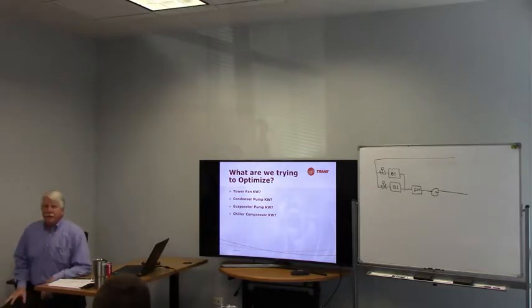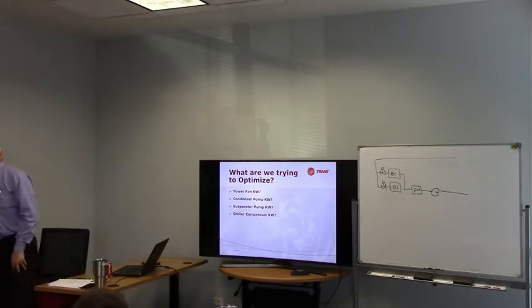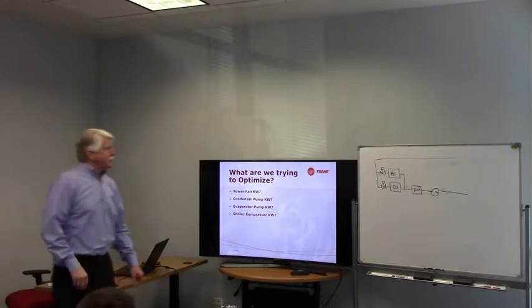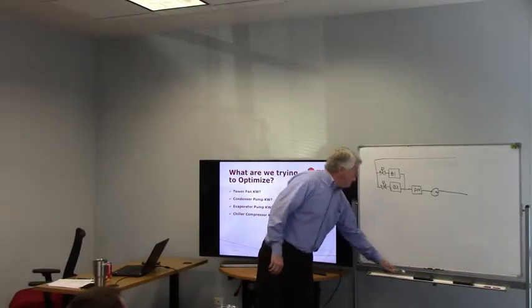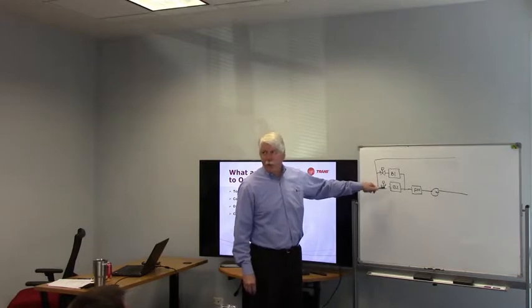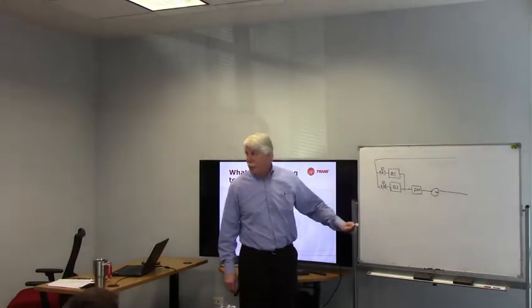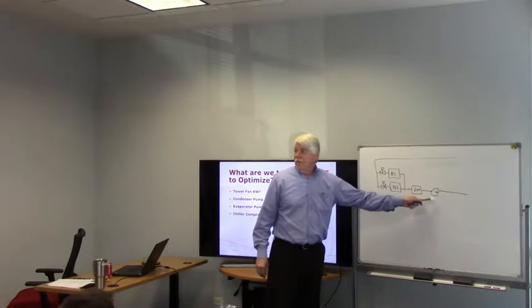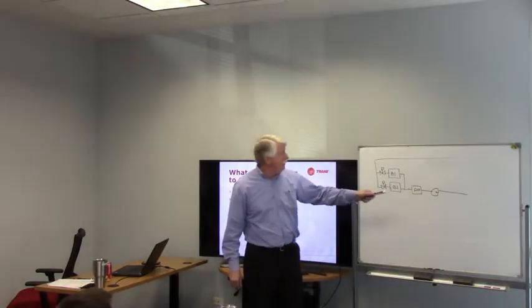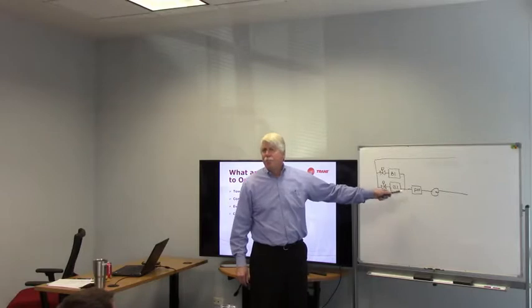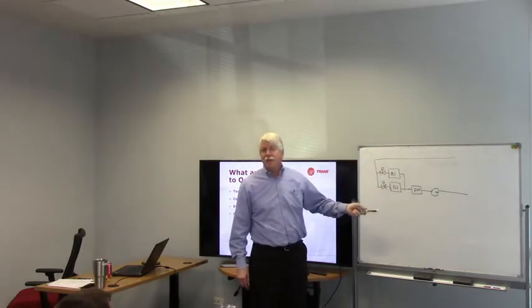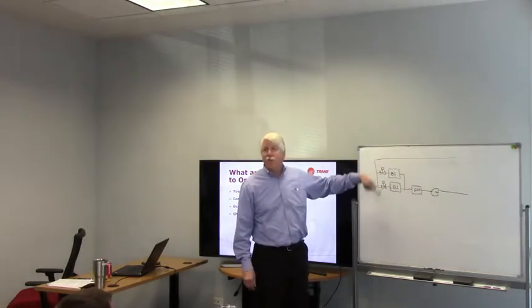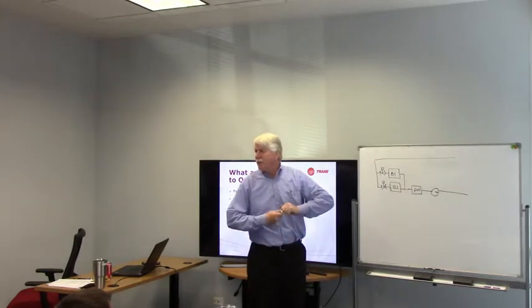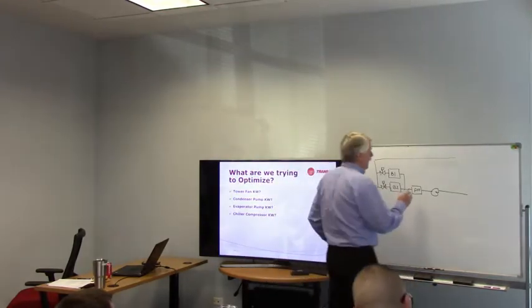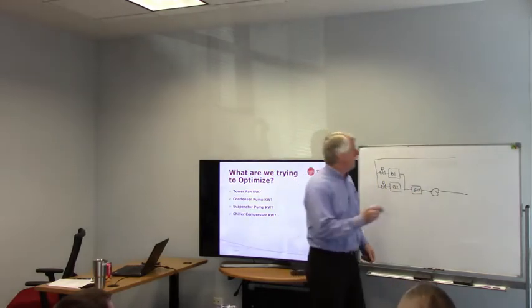Nothing is more fun than real life lessons. So I'm going to invite Mr. Cutts up to explain something. This was a project he was on where we had a couple of boilers. It was actually a variable primary system. They put in a flow meter, and Kevin had some DDC loops running to maintain different flow rates depending on how many boilers are running. And they obviously had to put in a bypass valve for it.